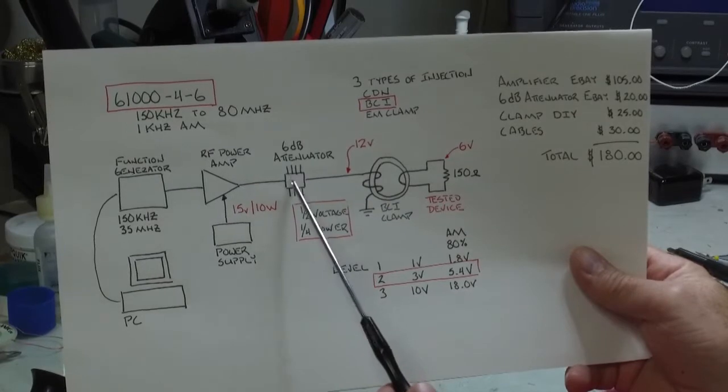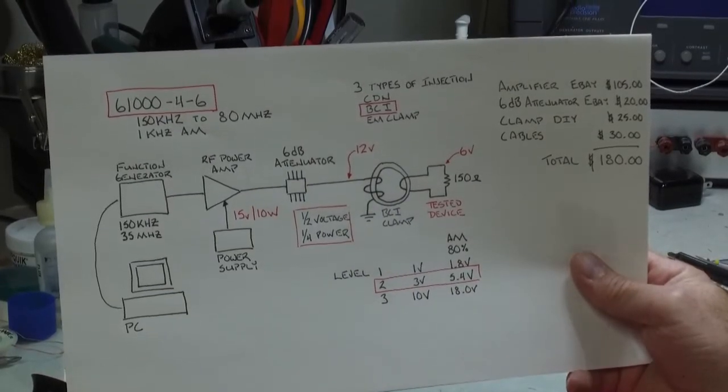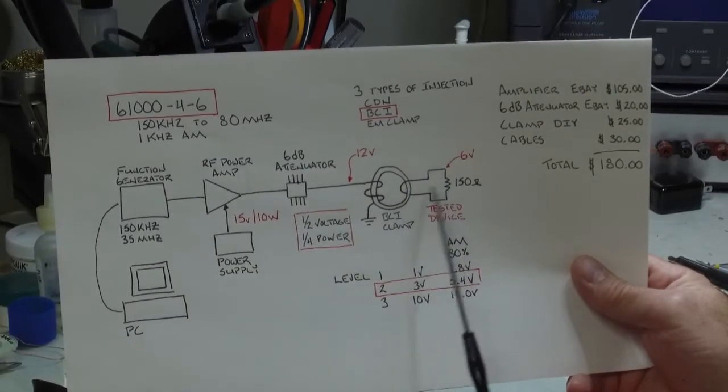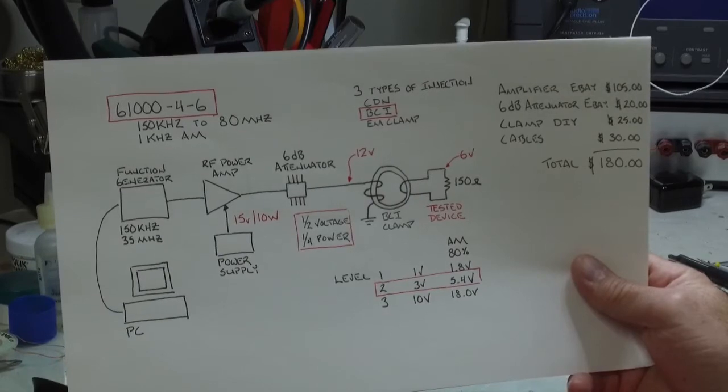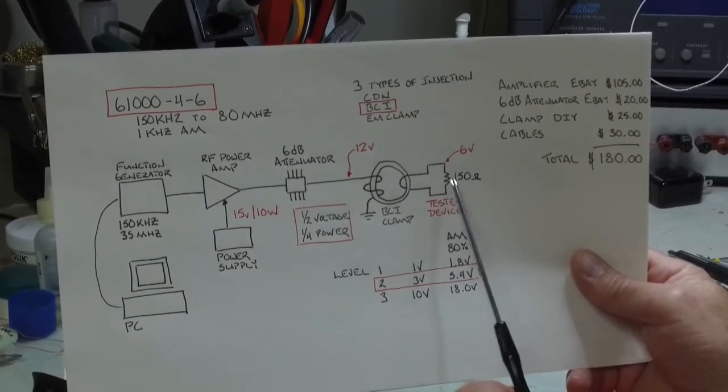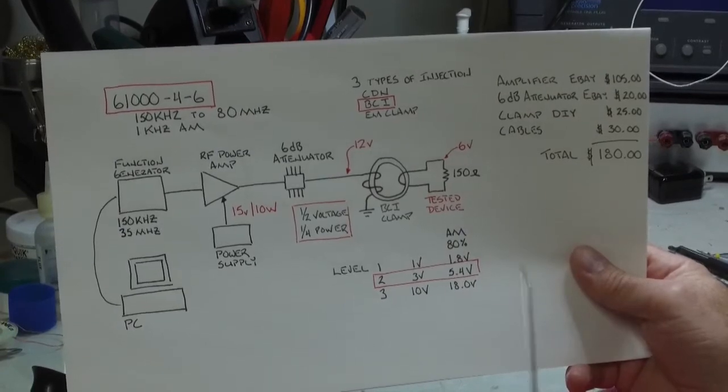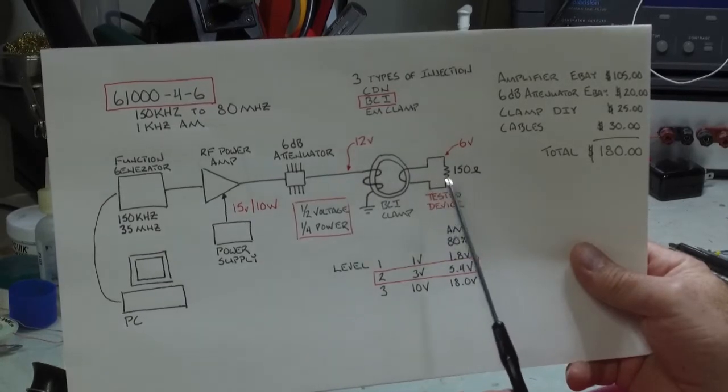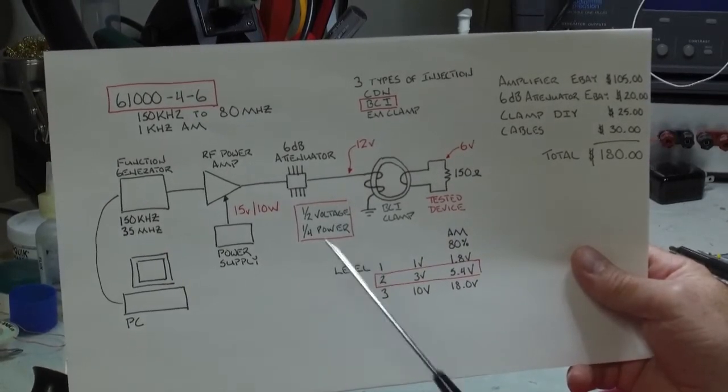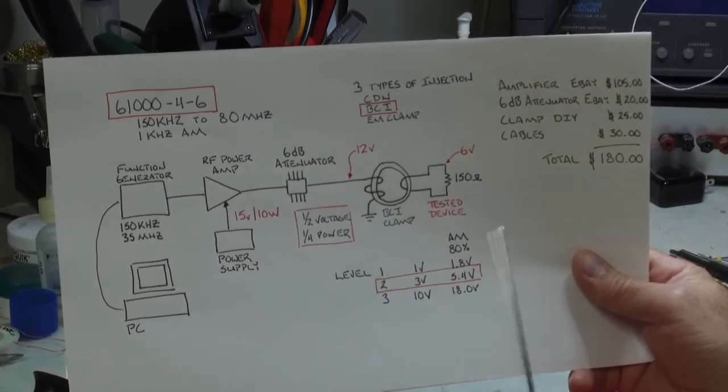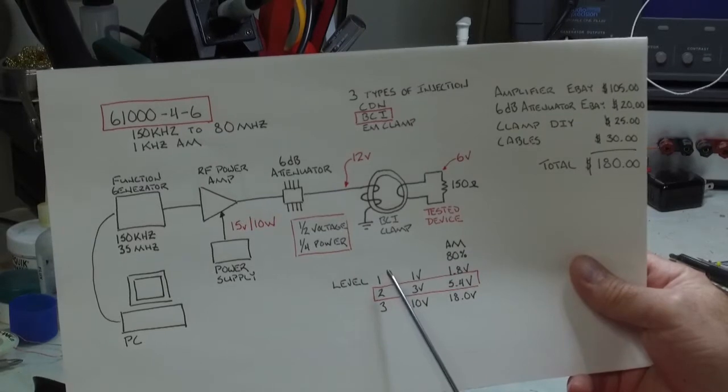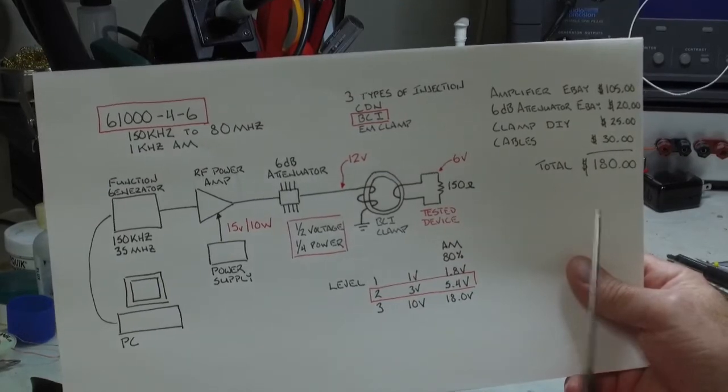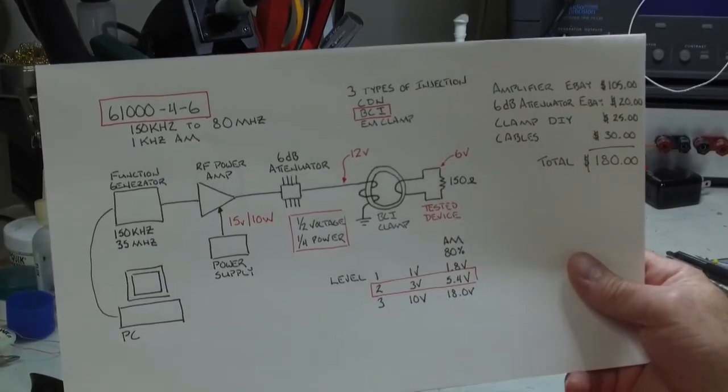So you can see the amplifier, the function generator drives the amp, goes to the attenuator, goes to this bulk coupling clamp, and I'm showing one loop through and the specification notes that the typical impedance is 150 ohms. And so I have my scope attached across a 150 ohm load, single turn through the toroid to measure my voltages. The specification notes three levels, level one, two, and three, which correspond to one volt, three volt, and ten volts that need to be induced onto this 150 ohm load.